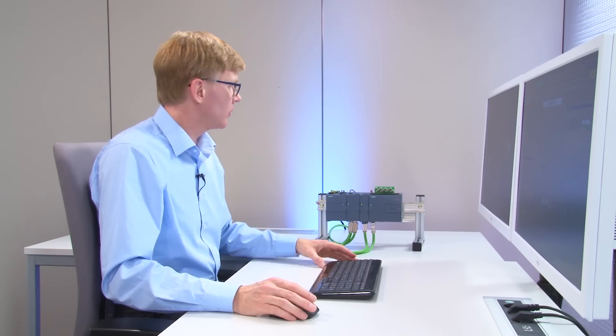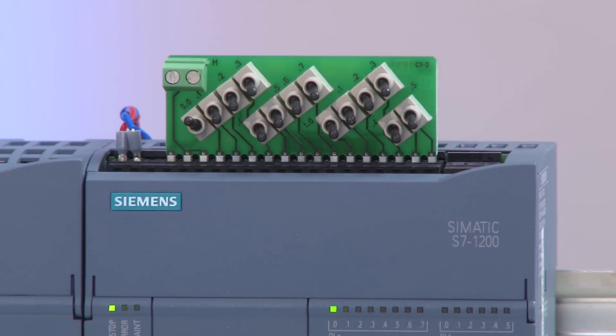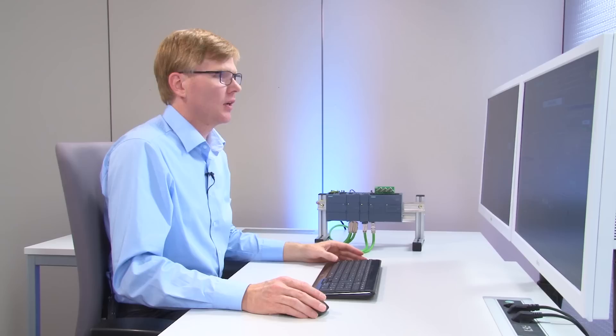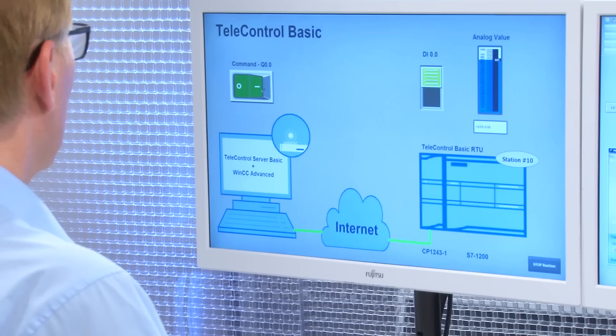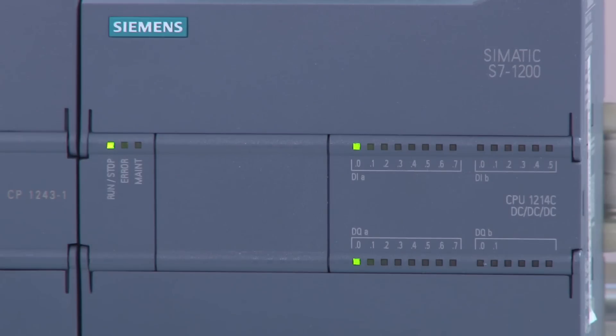If we now create a message by activating the switch 0.0, the status change will be transferred immediately to WinCC and displayed on the image object. The analog value is also transferred event-driven and displayed on the WinCC image object. Now we send a command from the control center to the station and it is immediately relayed to the digital output. As you can see, we've configured the basic functions of a Telecontrol BASIC station along with the Telecontrol Server BASIC and put them into operation. By configuring the data points in the S7-1200 RTU, the relevant items are automatically created on the Telecontrol Server BASIC OPC server once the connection is established. They now only need to be linked to the images of the HMI system.